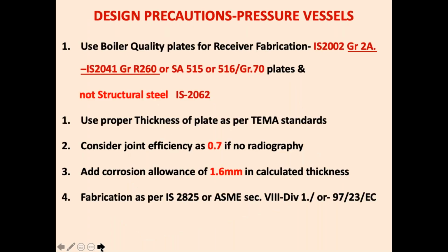The next very important design precautions are for pressure vessels. Always use boiler quality plate. Since this plate is not readily available from SAIL, Steel Authority of India, IS 2002, a lot of people use 2062, which is a structural steel and not a boiler quality plate. Its carbon content is very high and it can lead to cracking of the vessels. So IS 2002 grade 2A or SA 515 or 516 grade 70 plates should be used for receiver fabrication, condenser shell fabrication, chiller shell fabrication, etc.